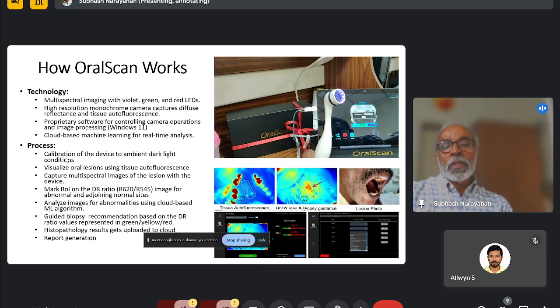So what is to be done is that the device needs to be calibrated to the dark light conditions, that's the ambient conditions in which the measurement has to happen. Why are we using dark light conditions? Because the re-emitted light from the inside of the tissue is very low in intensity, and if you do it in a normal room condition, the sensor will get bleached by the high intensity. What we have to look at is the diffusely reflected light and the fluorescence emission, which needs a dark room environment to capture. First the camera is switched on, and then we can visualize the oral lesion using the fluorescence mode.